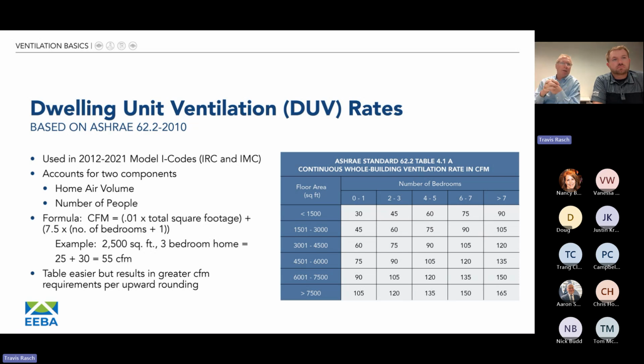So in an example, a 2,500 square foot 3-bedroom home, 1% of 2,500 is 25 CFM for that half of the equation. And then 7.5 times 4 is 30. Add those together, this home needs 55 CFM. It should constantly be pushing 55 CFM of bad air out and pulling in 55 CFM of good fresh air. If you don't like even that formula, the code also has the table on the right, which gets you to the same place, just in table form.